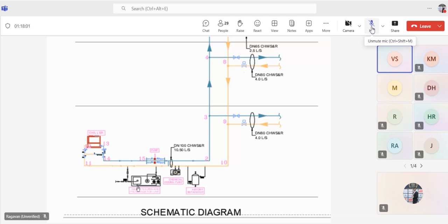Okay. Usually there is a scenario: when you do the design, whether based on an app calculation, any other software, or even manually, there is a value that will carry. When you do the selection, you will not get the same value as per your design. The value will change, maybe 5% or 10%. That's the reason I told you to consider a safety margin. Otherwise the pump will not be enough, because sometimes a building has restricted flow. For example, in a district cooling system, each and every building and each and every plot already has an allocated water flow rate. So you have to adapt within this flow rate.